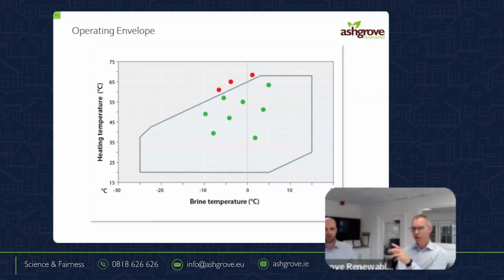It never could. So there's two things there. We can either design out the problem, right? But there would be scenarios here where, if you can imagine, this is a ground source heat pump, but it could actually not be. I could be just using this heat pump to take heat from an abattoir. And imagine if I needed to produce water at minus 15, so I have minus 15 degree water leaving my heat pump to go cooling something. Well, in that case, if I'm operating at minus 15 to cool something, the maximum temperature I can get out on the hot side here now is 50 degrees.